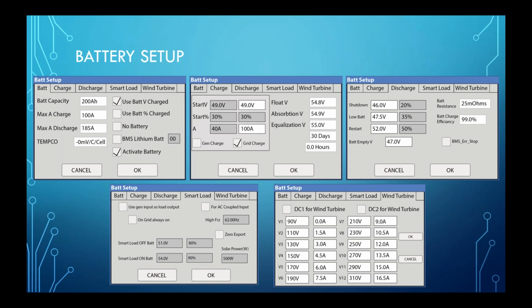It does come preset with some settings that are actually preset for our batteries, the PCCs. So if you are using lithium batteries or lithium-based batteries, please, please, please make sure you change these values to reflect the battery that you're using. Because we do not want to overcharge or do anything that the battery won't like, especially if the BMS can shut down in those instances. So pretty straightforward. The battery capacity at the top on that very first tab will be the total amount of amp hours. Your max charge and discharge are typically determined by the battery manufacturer themselves, and then by the number in parallel. TEMPCO is important for lead acid type of batteries, not very big for lithium.